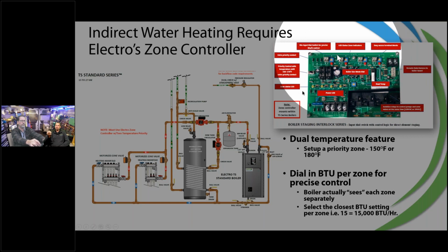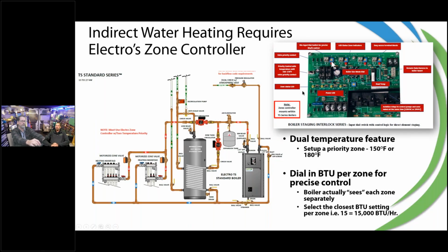Up there you'll see some dials, little red ones. Here we have the ability to dial in the system. Going for 15 tells me that's a 15,000 BTU zone, even though it might be a 20,000 BTU boiler or bigger. If I dial it into 15,000, anytime that zone calls, the boiler won't give you any more energy than those 15,000 BTUs. So we can really adapt the boiler to the zoning, which is pretty wild, and that's something we've never been able to do before.